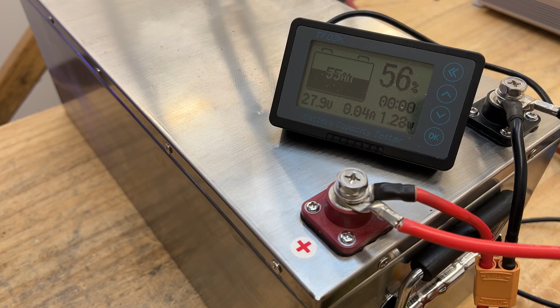So let's see how long it takes for this battery to cool off and for the BMS to start again. This is a sealed battery, it doesn't have a fan - if it had one, it could cool the BMS quickly, but that doesn't seem to be the case here. So we'll just have to wait. All right, so it took about 15 minutes for this to cool off and for the BMS to kick back on. So we're going to start our test again, this time lowering the amount of power.